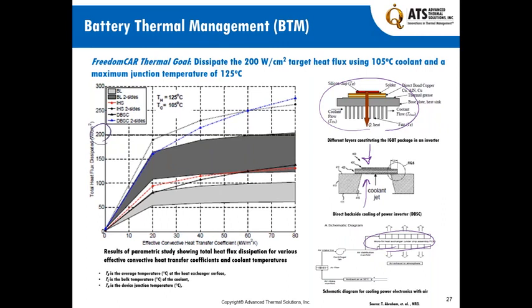Our coolant temperature is about 105, and the hottest temperature T-sub-H associated with this assembly is at 125. Anything that falls in this area is a possible solution for me. The important thing to look at, and bring it down to this axis, is the effective heat transfer coefficient - you can see this ranges from about 30 to about 80 kilowatts per meter squared per degree K.